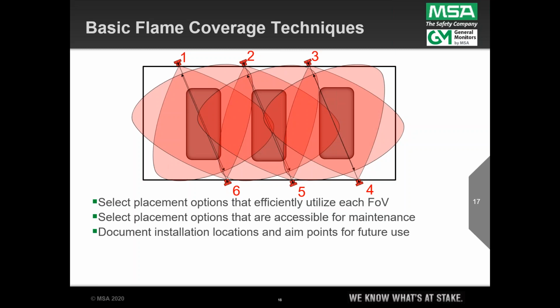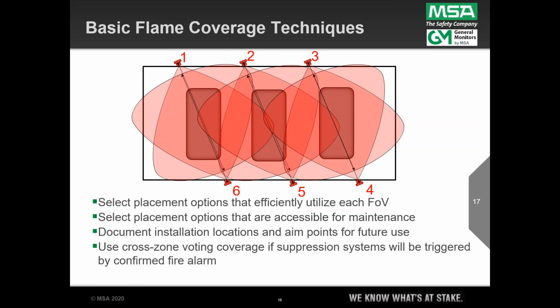So if I have to take one down, using just geographic coordinates, I can identify where to replace it and where to re-aim the laser aiming device, that green dot where I documented its coordinates on the floor. I can put the laser aimer back on there, put the dot back on the spot that I had documented earlier, and replicate its alignment angle. And then if we are going to drive a suppression system, a best practice here is to use cross-zone voting, where I require two detectors in alarm before I dump some type of water deluge or releasing system.